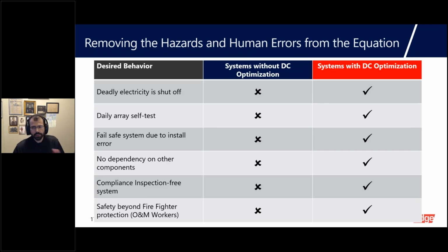So just to summarize, I'm not going to read through it, but here's a quick summary between systems without DC optimization, or without MLPE, and systems with DC optimization. Without DC optimization, voltage is always capped at 1,000 volts as long as the sun is shining. If there is a problem with the array, it's not a fail-safe system. There is a dependence on other components, like I explained, hazard level 3, which requires other protective measures in the array.